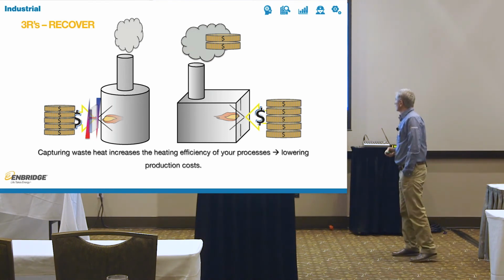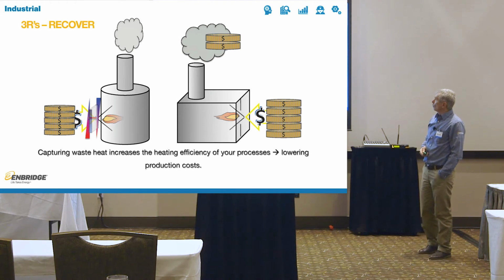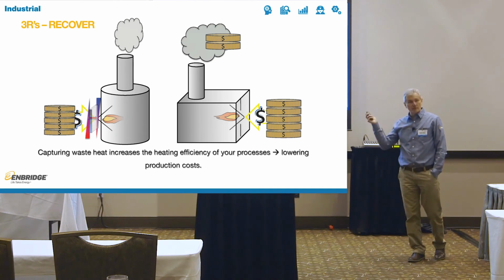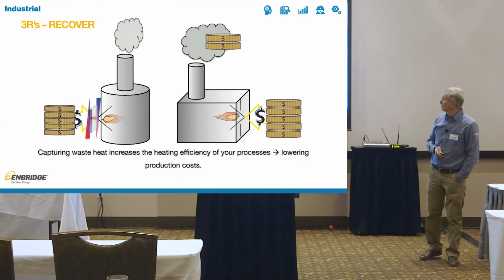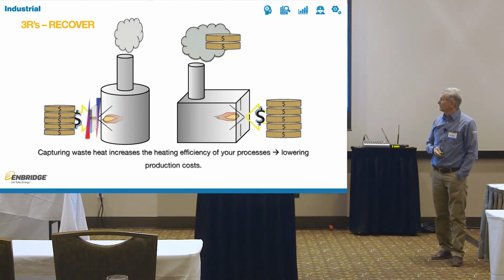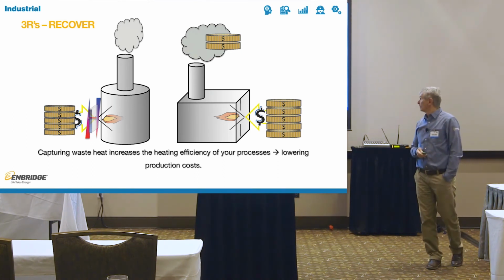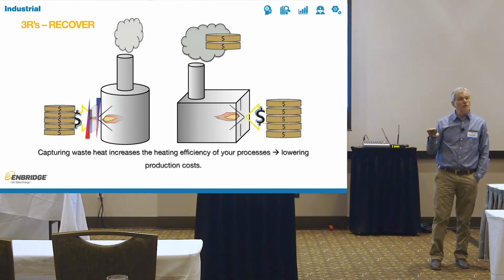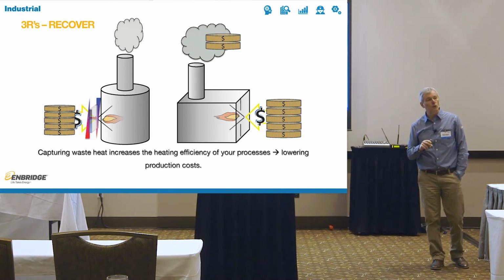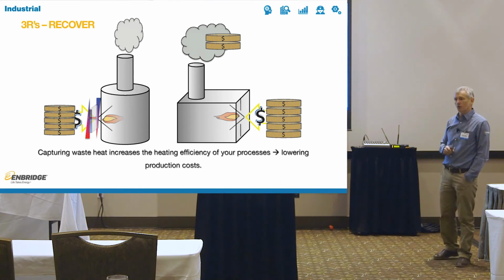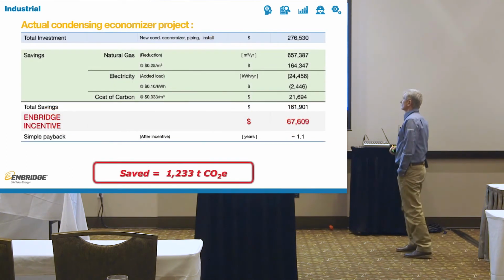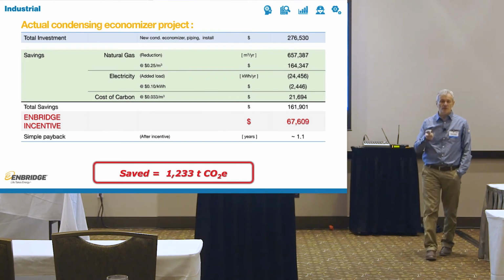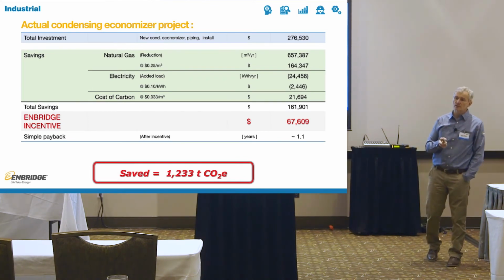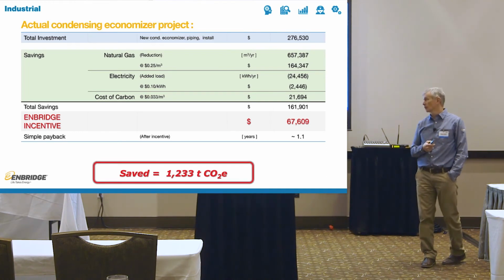So what we've done, instead of taking all this money, putting it up the stack, and the money that goes up the stack from the other piece of equipment, we actually took some of this exhaust, preheated the air going into the direct water heater, and reduced the amount of energy needed in the direct contact water heater. In the end, we actually ended up eliminating the direct contact water heater altogether and using only the boiler for all of it with the condensing economizer. This is why I love condensing economizers. If you're going to do anything and you have a process water requirement, a condensing economizer is the way to go.